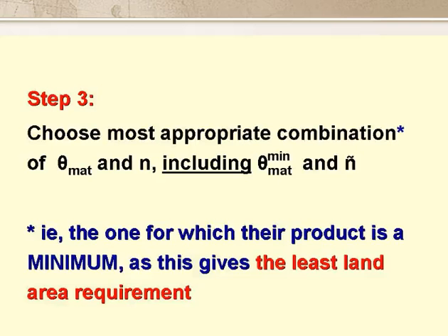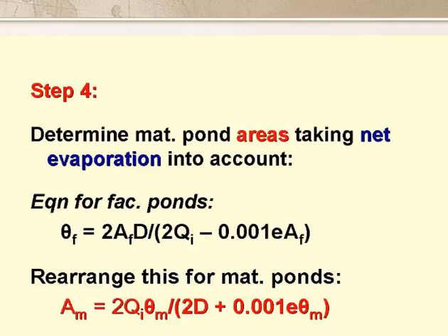Step 3 is the selection of the most appropriate combination of theta mat and N, including theta mat min and N*, where N* is the value of N for which theta mat first goes below theta mat min. Step 4 is the calculation of the maturation pond areas, taking net evaporation into account. With facultative ponds we had the first equation shown on the slide, and for maturation ponds we rearrange this equation in terms of AM, as shown in the second equation on the slide.